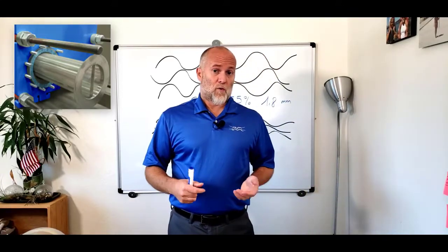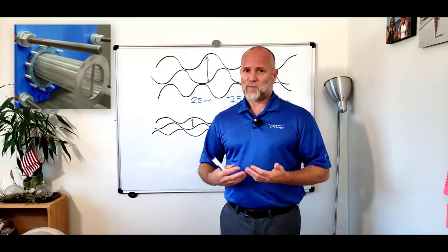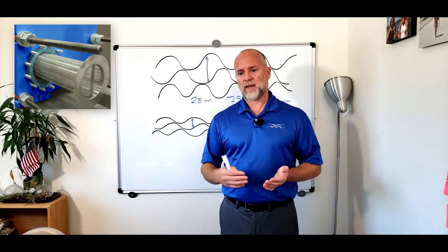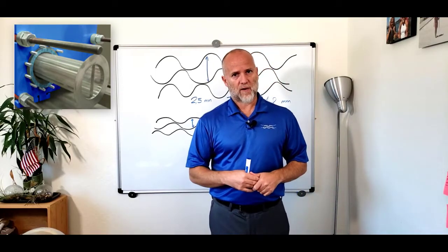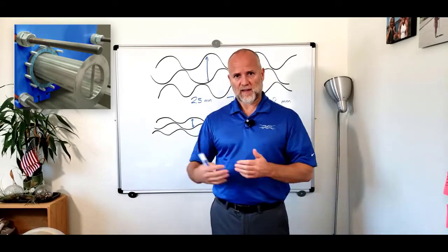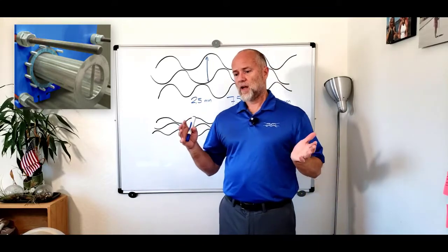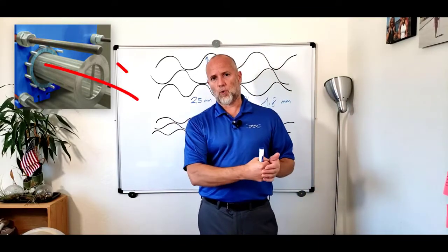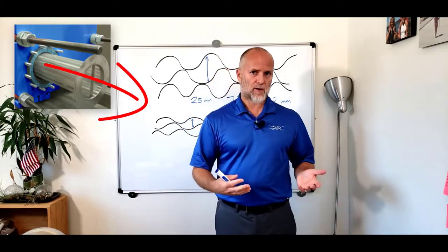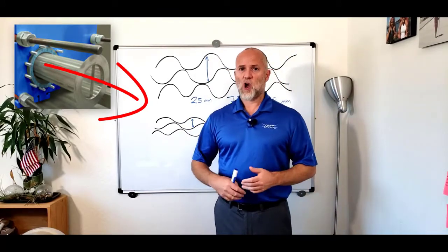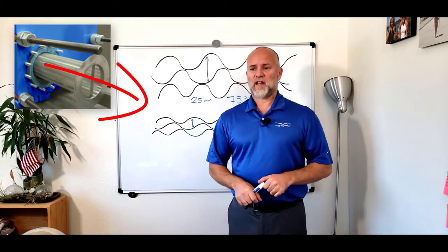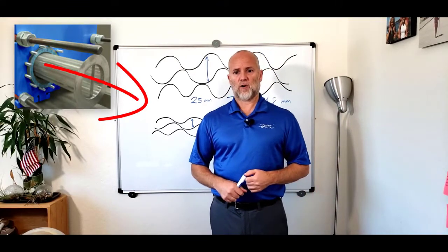In theory, you can have port filters in the four ports, but it doesn't really make sense. You want port filters normally only in the inlet of the cold water coming from the cooling tower, or from the chiller, in any case, the cold inlet. As you can see, you pull the port filter out from the inspection port on the back, so unlike a strainer you don't have to disconnect the heat exchanger. Of course, as with the strainer, you have to stop the flow and close the valves. But other than that, it's a minor disruption of your operations.